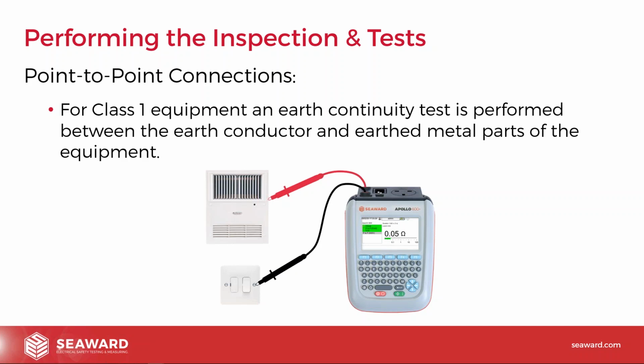So for class 1 equipment, we do an earth continuity test. Quite often this is performed between something like exposed metal parts on the equipment, like the fan there, and an earth metal part in the installation. So this could even be just the screw on the fuse spur. Obviously, if you want to, based on the risk and isolation, you can further dismantle it and check the earth terminal inside, but generally with fuse spurs, due to their construction, the screw will always be connected to the main earthing terminal within the fuse connection unit. So a lot of times it's lower risk, and a lot of companies offer this as a low risk option, and they do point-to-point testing where they check from the earth screw on the spur through to the body of the equipment, like a cooker or a fan or whatever, to prove that there is an earth connection and that the equipment is earthed.